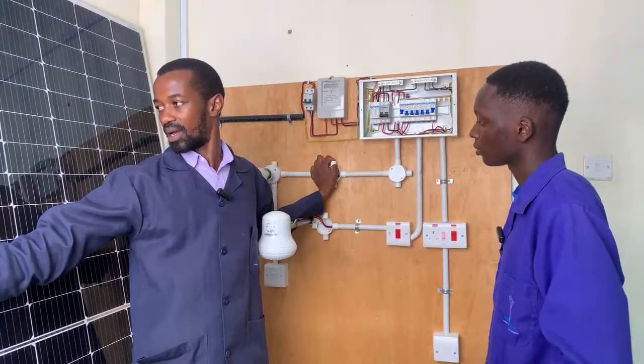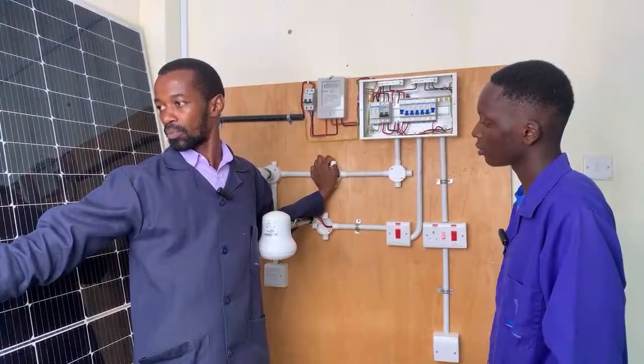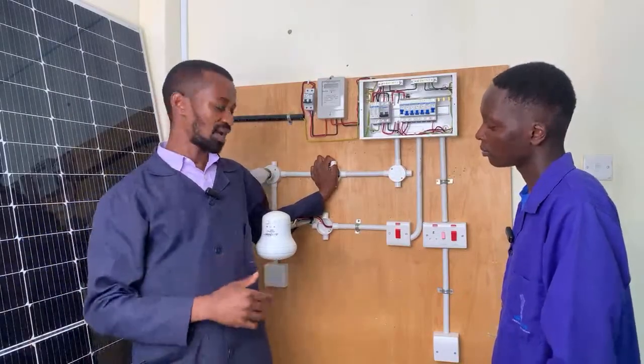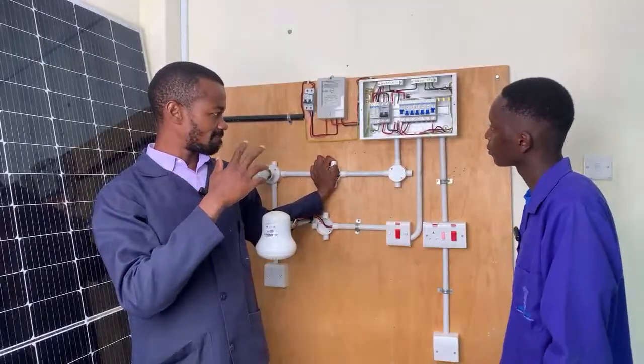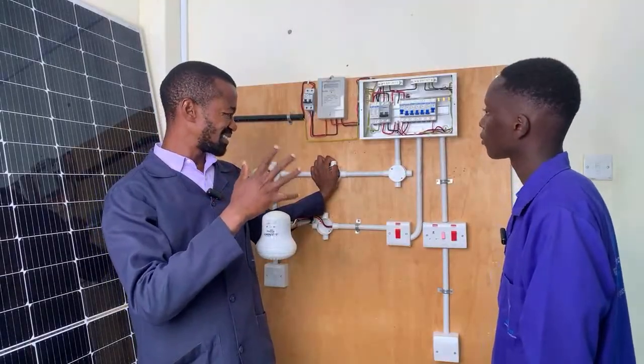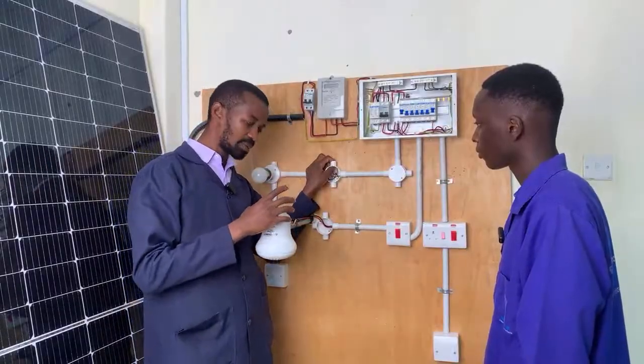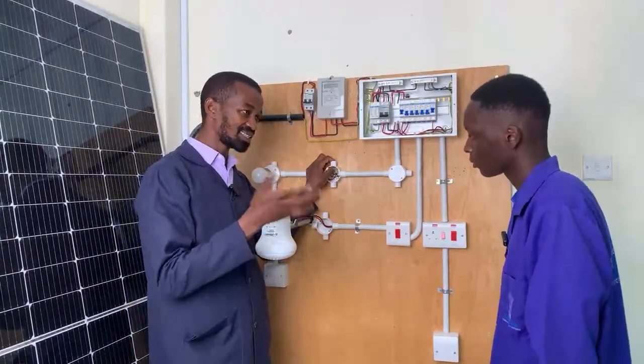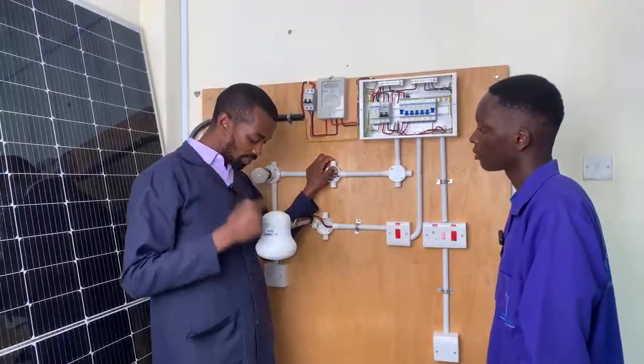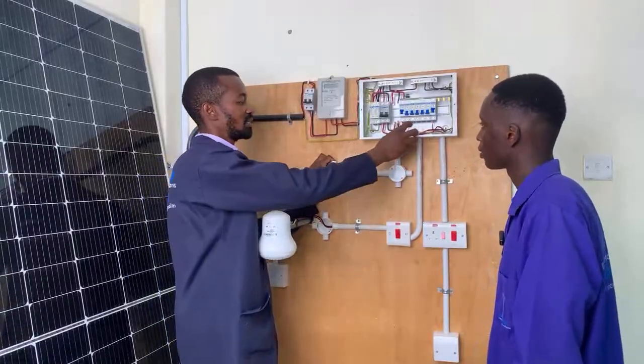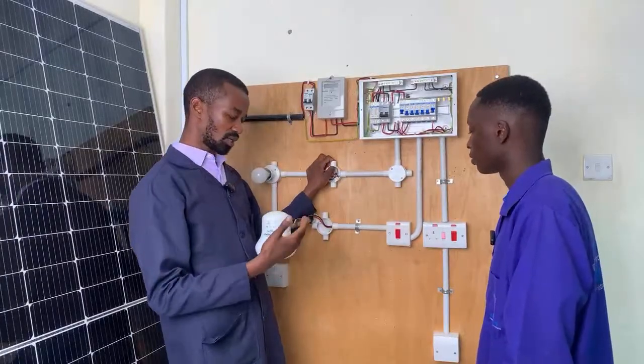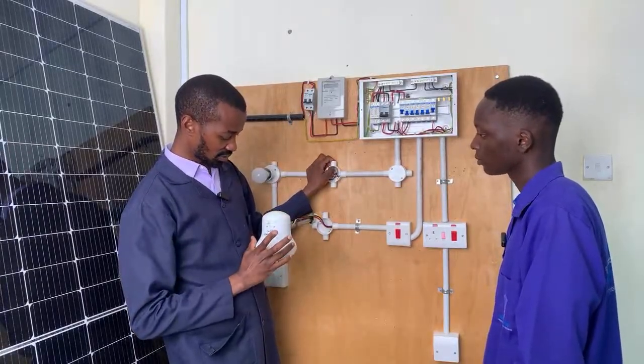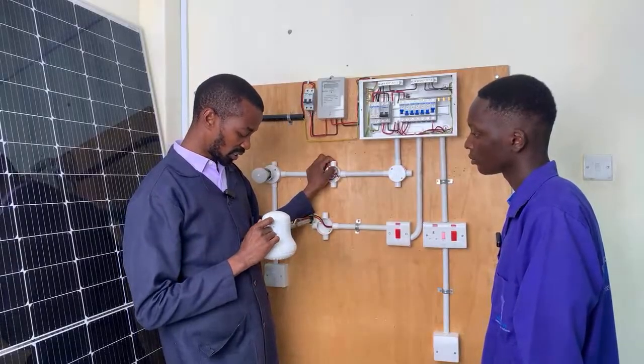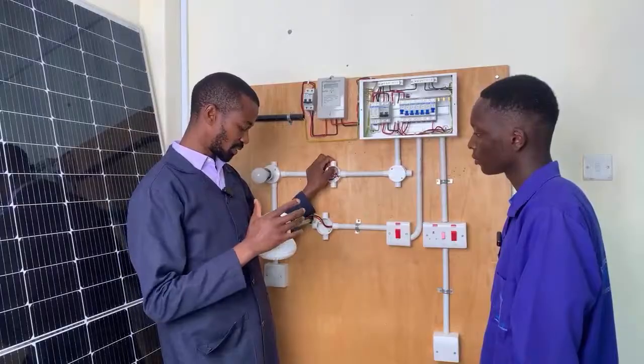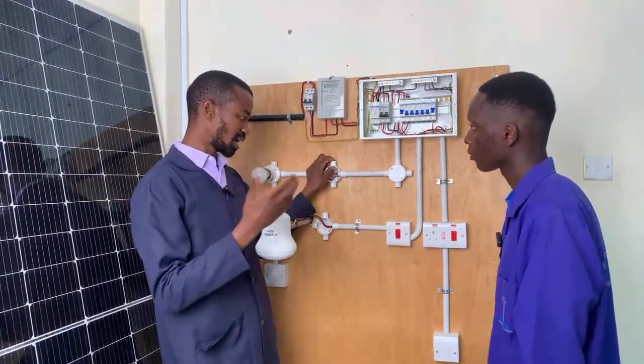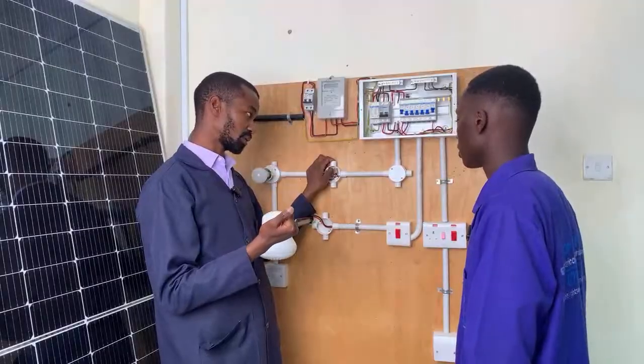When it comes to the ideal size, it has to be probably 6. So if someone decides to replace this instant shower head with a bigger one, a 6 mm cable will accommodate that without the customer having to change the whole wiring. So at the point of installation, even if the customer later replaces it with a bigger unit, the existing cables will still be sufficient.